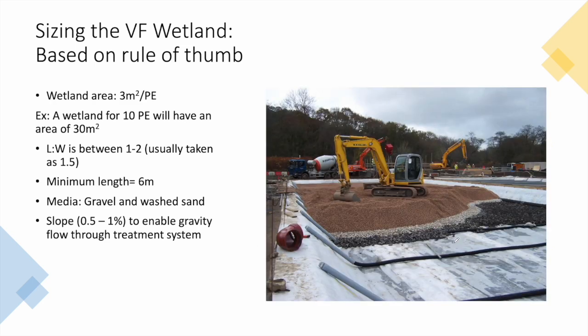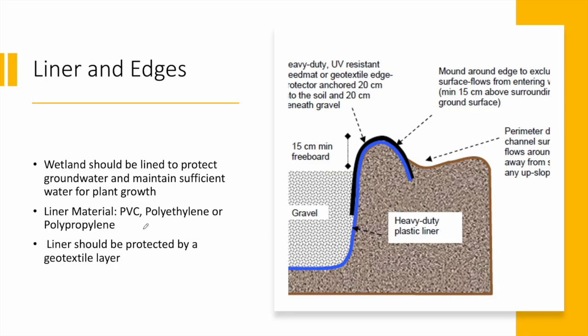The drainage pipe is a perforated pipe covered by coarse gravel, then finer gravel, then sand, and another gravel layer at the top. The wetland bottom must be sloped at 0.5 to 1% to enable gravity flow through the treatment system. The wetland must be adequately lined to protect groundwater and maintain sufficient water for plant growth. Liner materials can be PVC, polyethylene, or polypropylene, and it is advised to protect the liner with a geotextile layer.